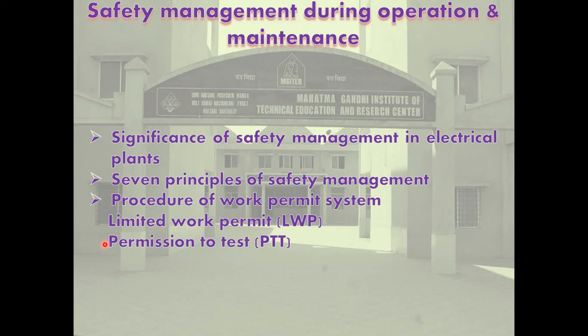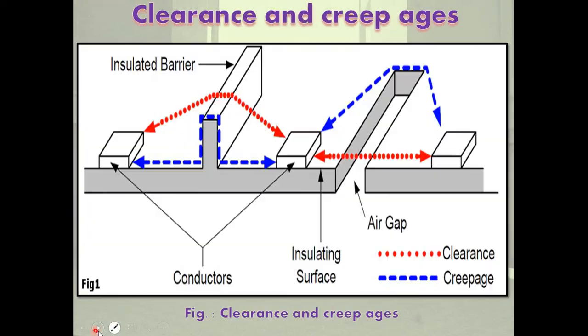similar to those during energizing. The table gives an example of a permit to test. Now, the testing engineer gives acknowledgement by signing on the copy of the PTT. The PTT is cancelled after return of the PTT by the test engineer. Okay, so these are all of the safety managements during operations and maintenance. Okay, now next is clearance and creepage distance and their significance.